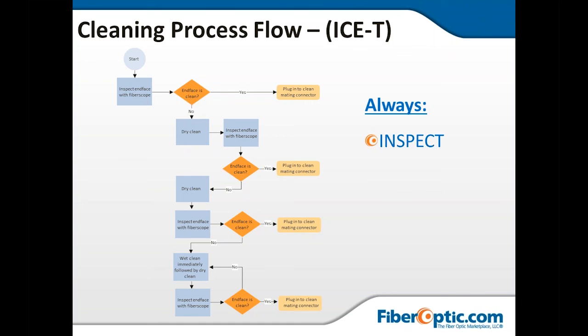We came up with an acronym for this, kind of an interesting side note, we thought of it during the summertime, so we named it ICE-T: Inspect, Clean, Evaluate, and Test. One thing to remember about the evaluation step is that a lot of people just say inspect, clean, inspect, test, but the evaluate portion means you have to keep going back. If it's not clean, go back and try cleaning with the dry method, maybe one, two, or three times. If that doesn't work, move to the wet method. That's the ICE-T method: inspect, clean, evaluate, and test.